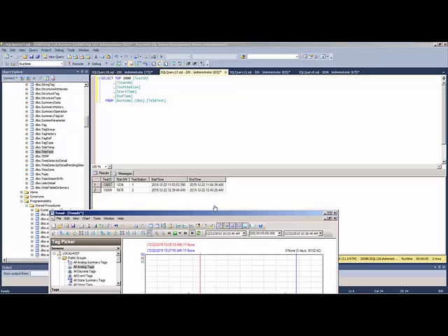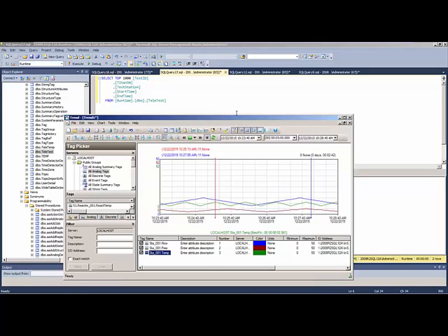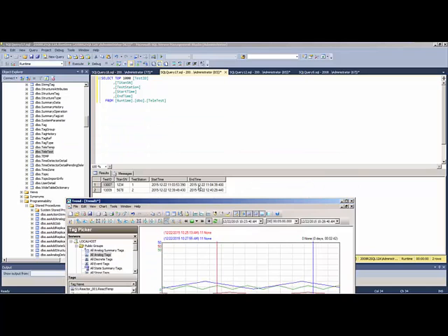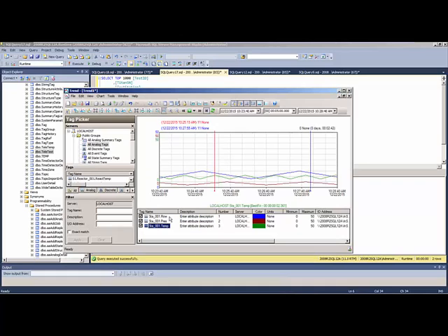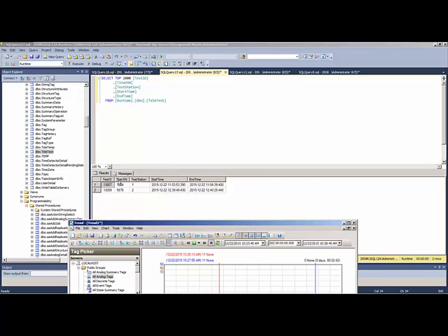Now that we have this information logged to the historian and to the test table, let's talk about how to extract that information. One way is to go to the Wonderware Historian Client — we know the start time, end time, and station number, so we can find the tags for station one flow, pressure, and temperature and dial in that start and end time. But that's tedious. The concept of this other table is that we store this information and can write a query to use the start and end time to extract that information directly from the Wonderware Historian.